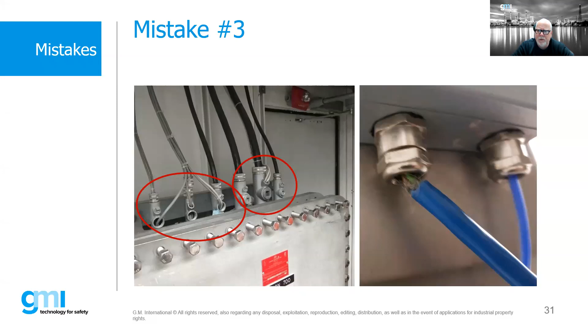Here are some other pictures, more from an installation standpoint. On the left we see someone used two different compounds, a liquid compound and a putty compound, to make explosion-proof or flame-proof seals going into a flame-proof enclosure. Those are definitely not certified. On the right, it's a little hard to tell, but what we see is an IP washer, which is appropriate for providing an ingress protection seal going into an enclosure.